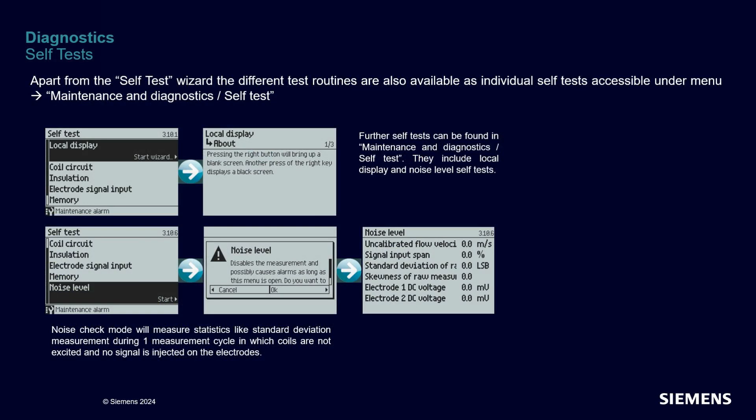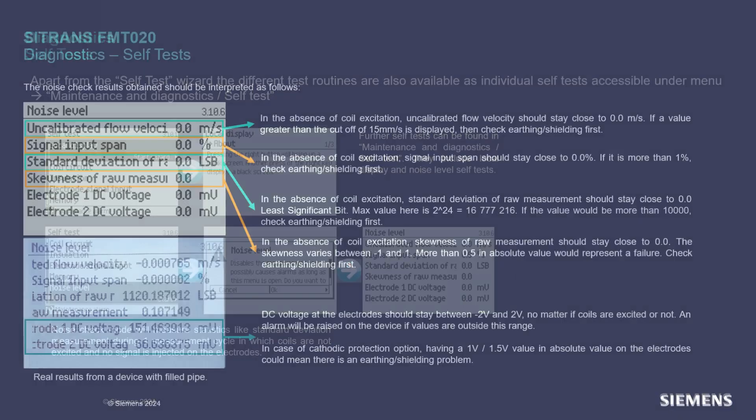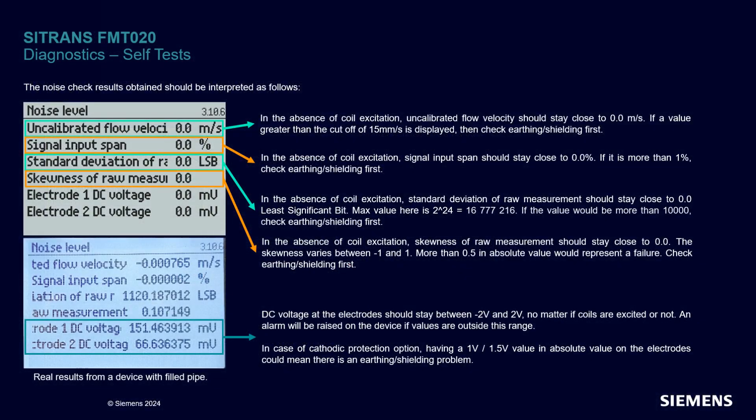You can also review the noise level characteristics to understand if there would be any kind of external interference that could impact your system and affect the measurements. When observing the characteristics of the noise, you can really troubleshoot the installation. It will help an experienced user detect grounding issues or other problems with the coils.